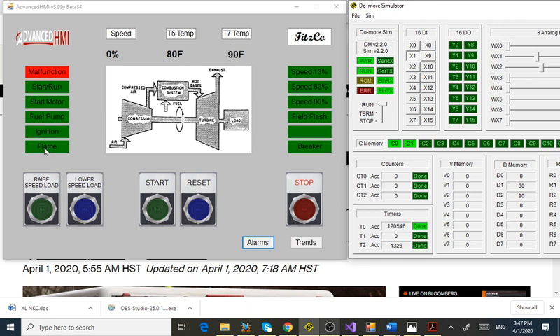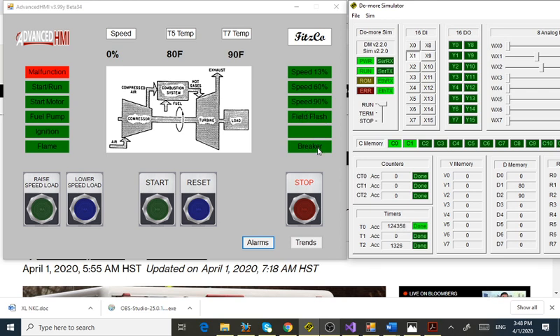These green blocks turn red when they're activated. Right now I have a malfunction of some kind. I have start and run — the start relay, when it drops out, means you've tripped. So it's a run relay. Then the starting motor, the fuel pump, the ignition — which is the spark plug — and flame, which in this case is just T5 above 400 degrees. Three speed relays, the field flashing logic, and the breaker closed.